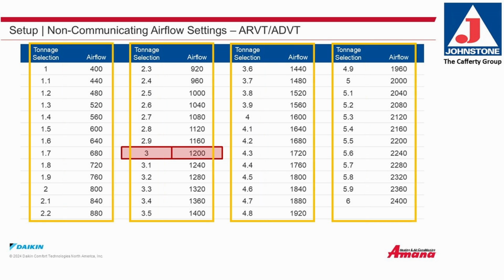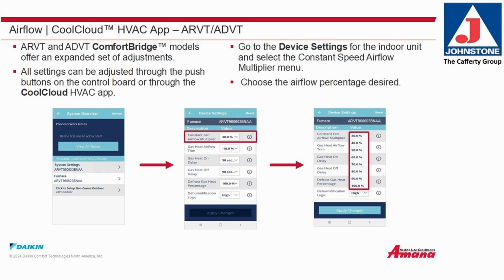Airflow setup using the CoolCloud HVAC app. ARVT and ADVT Comfort Bridge models offer an expanded set of adjustments. All settings can be adjusted through the push buttons on the control board or through the CoolCloud HVAC app. Go to the device settings for the indoor unit and select the constant speed airflow multiplier menu. Then choose the airflow percentage desired.